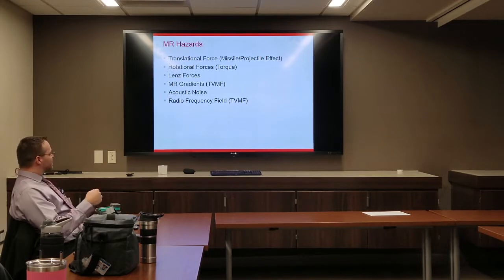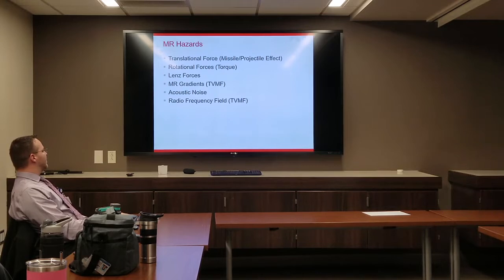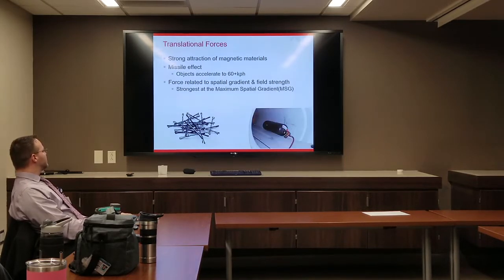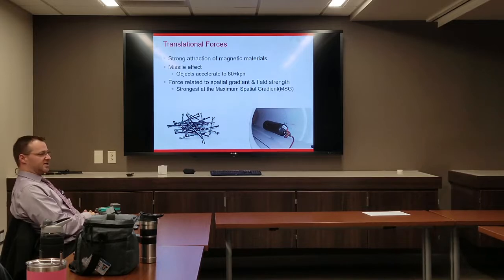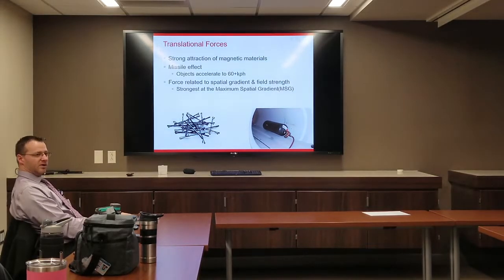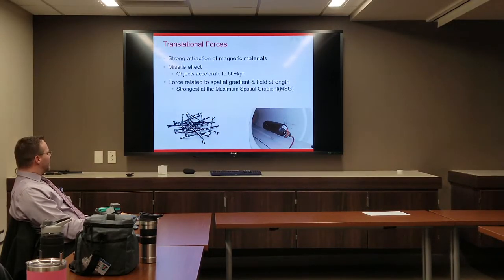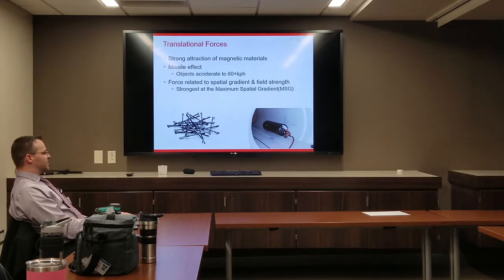MR hazards include translational force (the missile/projectile effect), rotational forces (torque), Lenz forces, MR gradients, acoustic noise, and radio frequency field hazards. Translational force is the strong attraction of magnetic materials — objects can accelerate upward of 60+ kilometers per hour going into the scanner. This force is related to the spatial gradient field, and the strongest pulling force will be at the maximum spatial gradient of that magnet.